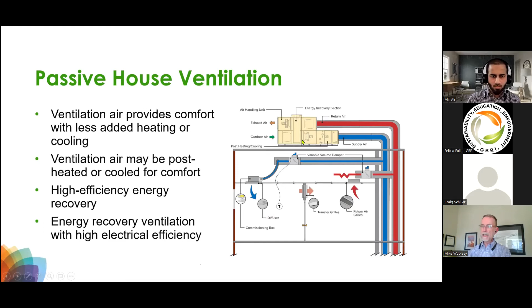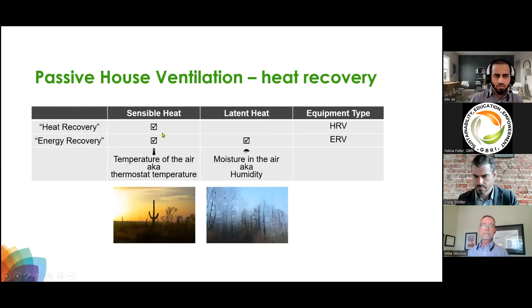And you also want to make sure that your ERV, as we call them, this air handling unit with energy recovery, is energy efficient. You can get these in 2 flavors. One that would address heat recovery only. That would be valuable for lots of Europe and also lots of the United States and Canadian West Coast. On the East Coast of the United States, though, from the Mississippi River towards the east, usually you're going to require energy recovery ventilation. The difference being that one handles just heat and the other handles heat and moisture. So what is then a typical ERV doing? I'm using the term ERV because that's passive house lingo. That's what passive house participants like to call air handlers of all sizes.